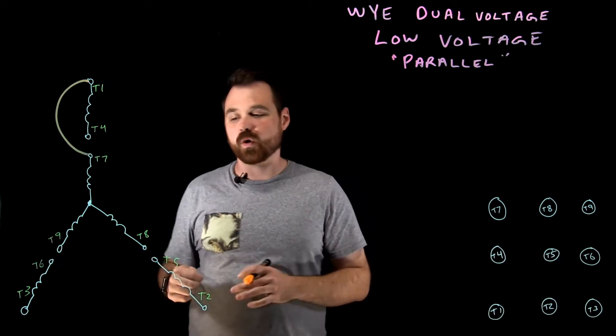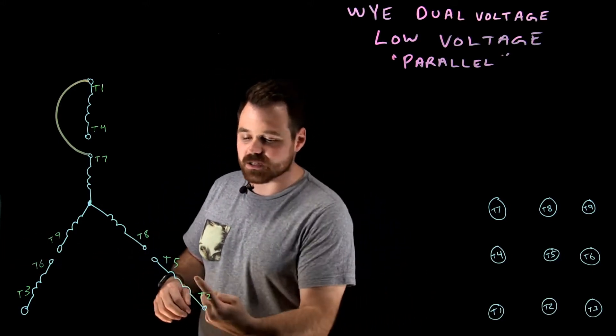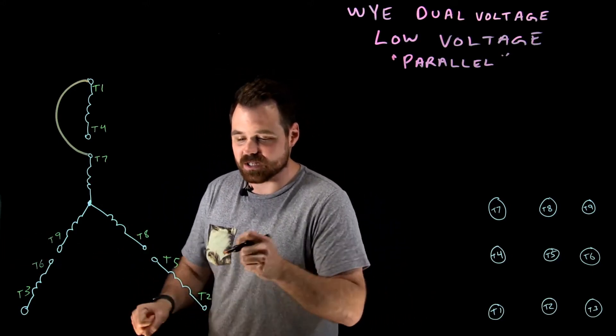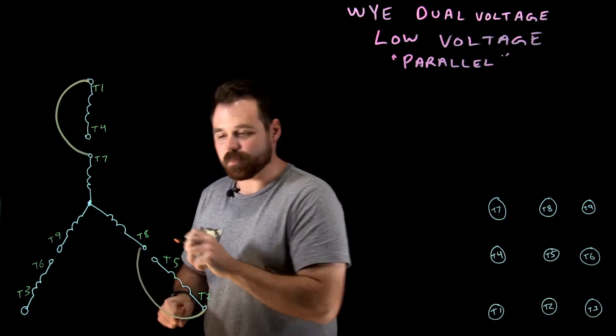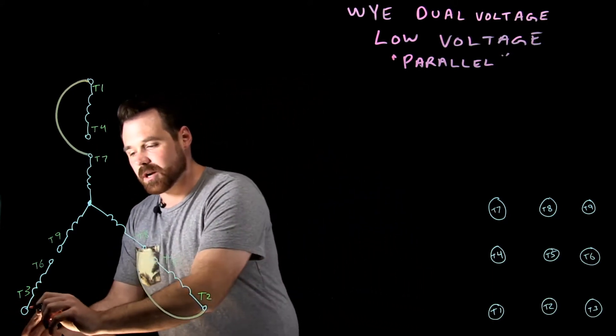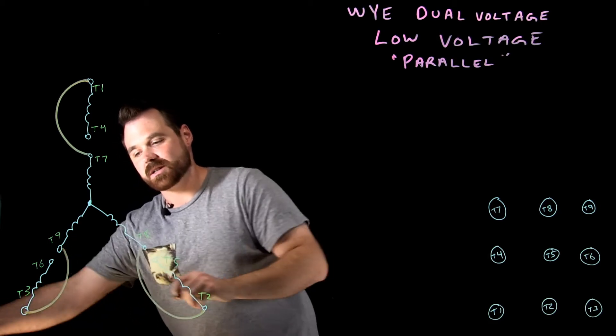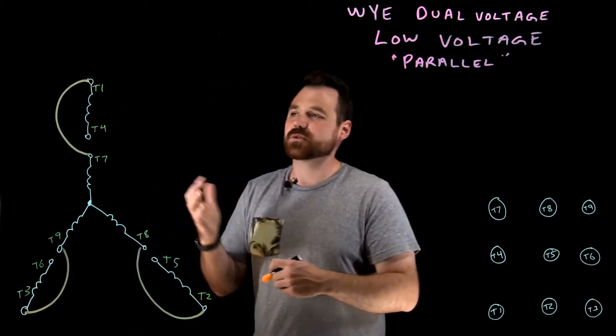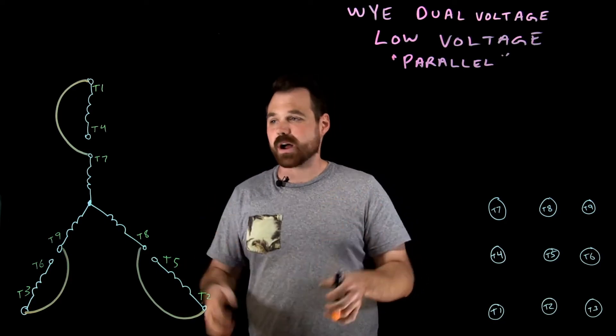Then we're going to do the same thing around the whole motor. If current is flowing into T2, I also want it flowing into T8, so those are in parallel. Same thing here - current flows into T3, and I also want it to flow into T9 at the same time, so those are in parallel as well.